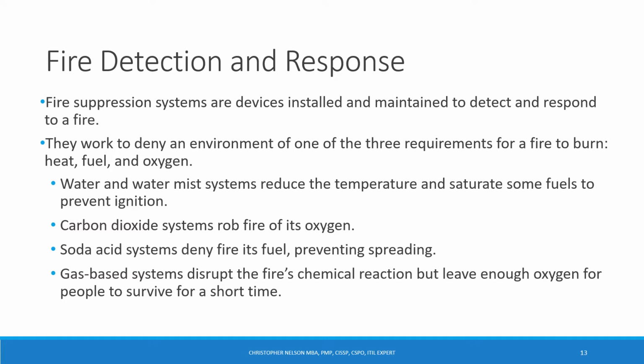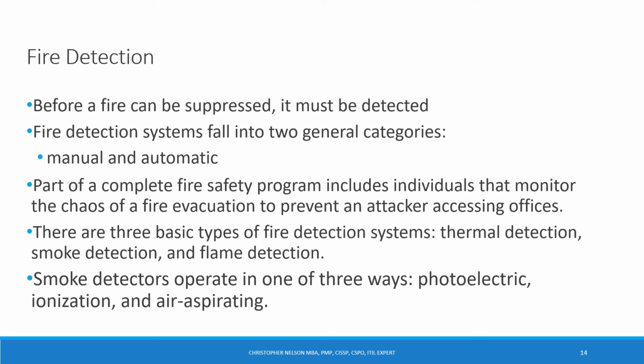Water mist systems reduce the temperature. Carbon dioxide systems rob the fire of its oxygen. Soda acid systems deny fire its fuel, and gas-based systems disrupt the fire's chemical reaction, but leave enough oxygen for people to survive for a short time. Before a fire can be suppressed, it must be detected. Fire detection systems fall into two general categories: manual and automatic. Smoke detectors can operate in one of three ways: photoelectric, ionization, and air aspirating. There are three basic types of fire detection systems: thermal, smoke, and flame detection.